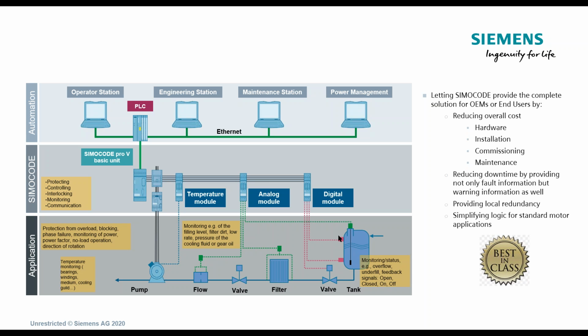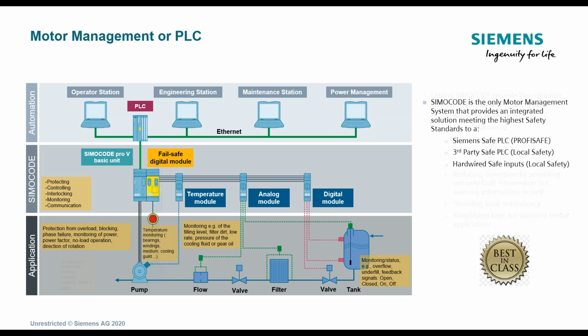And then, oh, here's the levels. I'm turning on and off. The SIMOCODE would control the pump for filling this, turning it on and off because of the level sensor that it sees. Or open this valve, and so forth and so on. So again, this is where it brings everything local to the SIMOCODE, and the controller just becomes, again, an alarm manager or a traffic cop to some of the signals that are coming in on problems that may be going on in the field.